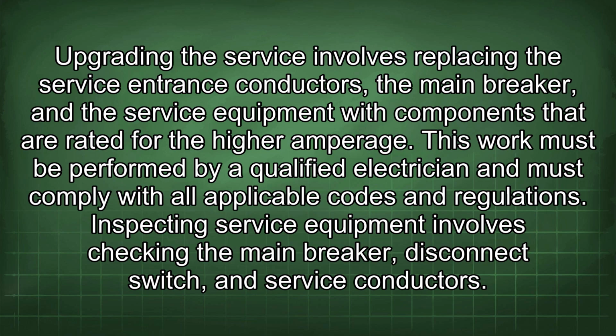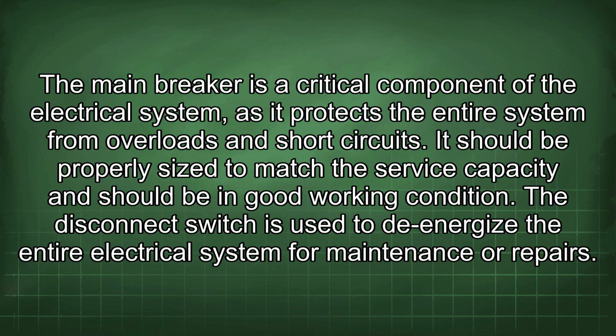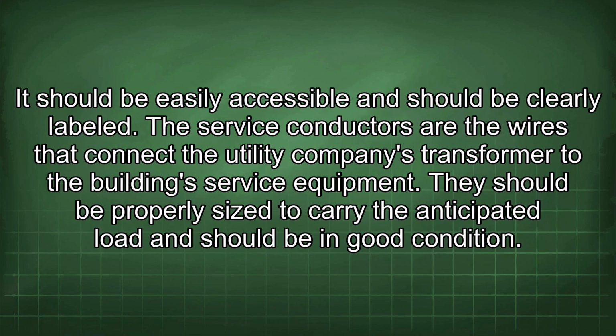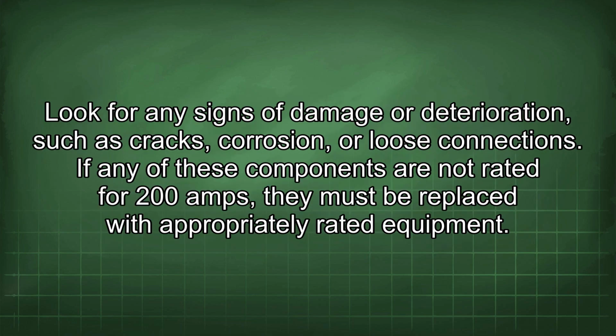Inspecting service equipment involves checking the main breaker, disconnect switch, and service conductors. The main breaker is a critical component of the electrical system as it protects the entire system from overloads and short circuits. It should be properly sized to match the service capacity and should be in good working condition. The disconnect switch is used to de-energize the entire electrical system for maintenance or repairs. It should be easily accessible and should be clearly labeled. The service conductors are the wires that connect the utility company's transformer to the building service equipment. They should be properly sized to carry the anticipated load and should be in good condition. Look for any signs of damage or deterioration, such as cracks, corrosion, or loose connections.